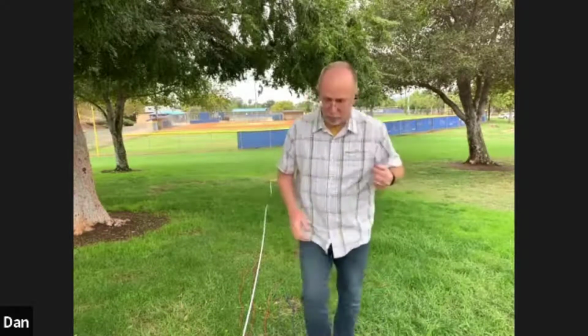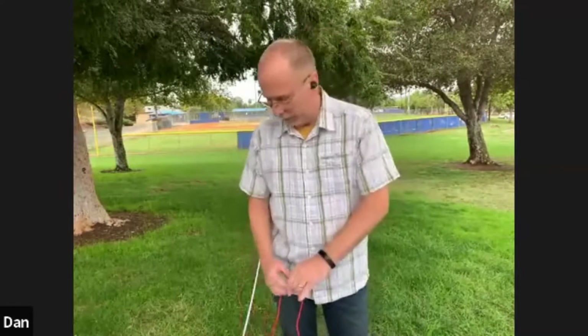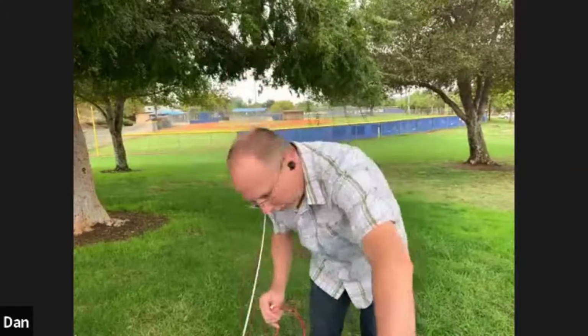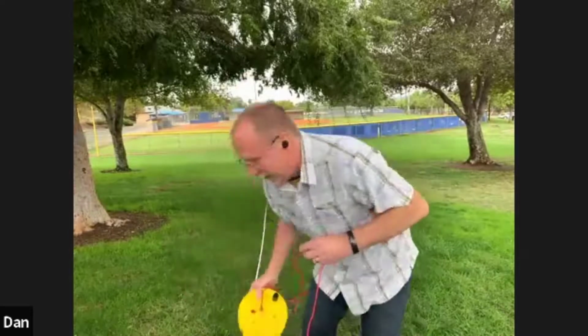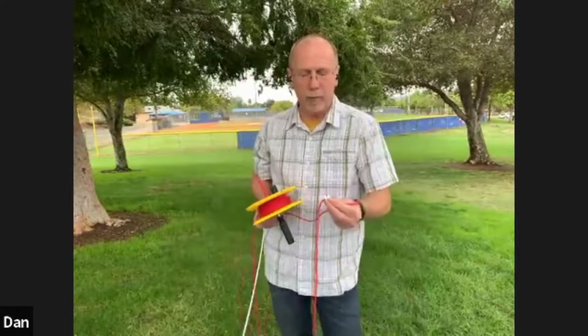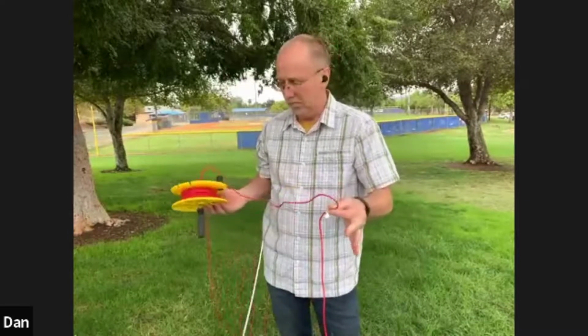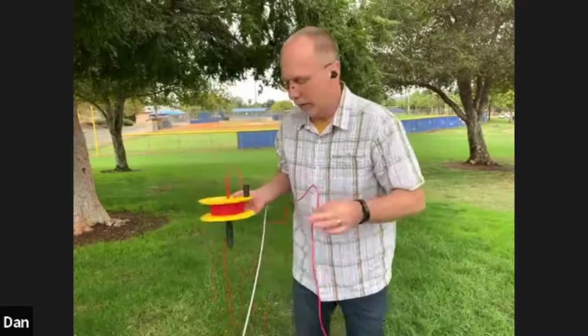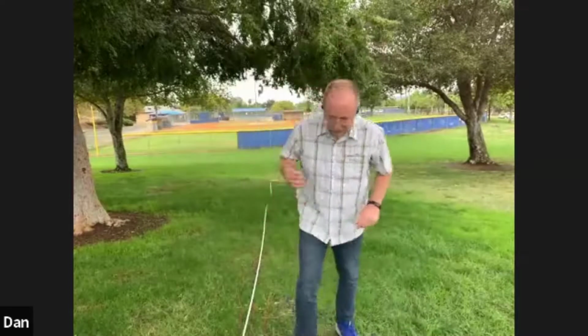Here's the other one. The way I've idiot-proofed it to a degree is I've put a little label on here that says stationary, which reminds me this red one doesn't move—it's just going to be there the entire test. The other thing I've done is put the 0 end of the tape measure at the ground rod and run it out the full 100%, 80 feet, and just leave the tape measure there.